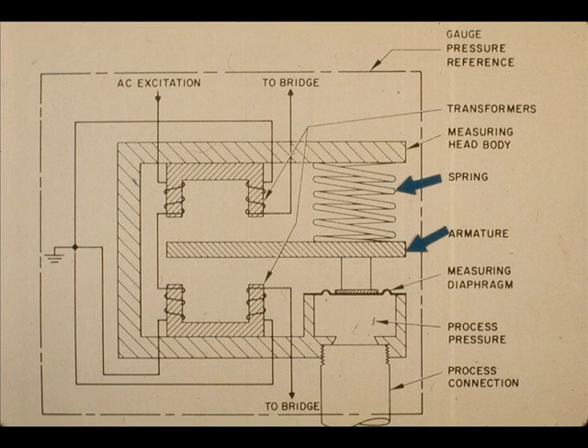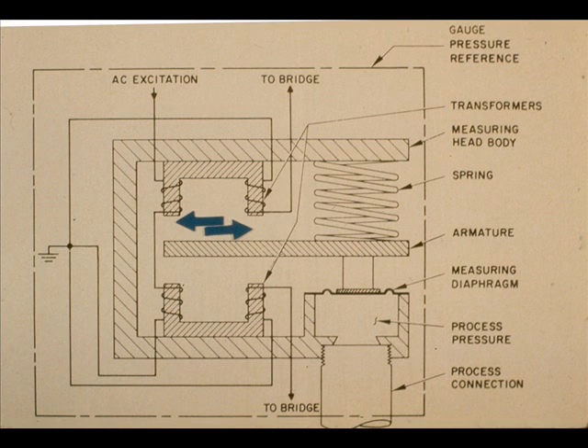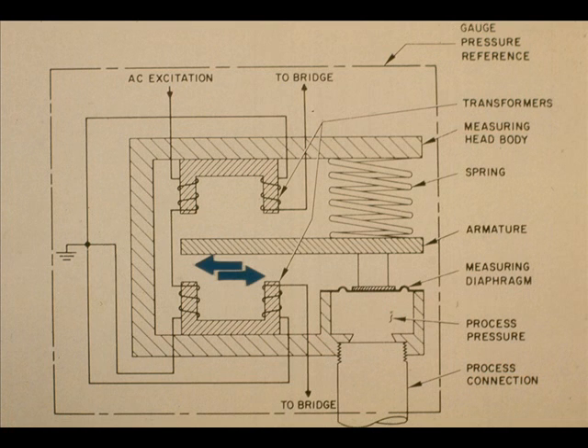Pressure on the diaphragm compresses the spring and moves the armature. This decreases the air gap in one transformer and increases the air gap in the other. From here, the operation of the Veritrac 56p is identical to the 56dp model for differential pressure.